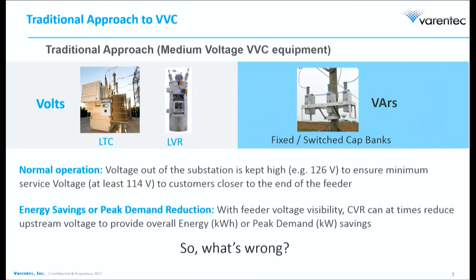So traditional CVR came in, as Burt explained, where you have medium voltage equipment you put in. You put cap banks and LVRs, where basically you try to reduce that slope by adding these boosts throughout the distribution system, reducing the slope of the voltage drop. This enables you to reduce the overall voltage coming out of the substation, and eventually reduce power consumption.